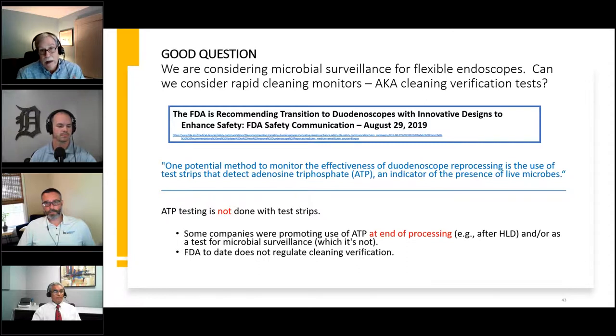Why that was problematic and confusing: ATP testing is not done with test strips, but apparently some companies were promoting use of ATP at the end of processing, meaning after high-level disinfection, and/or as a test for microbial surveillance, which it's not. Further discussions with and clarification from the FDA revealed they had concerns about the claims being made.